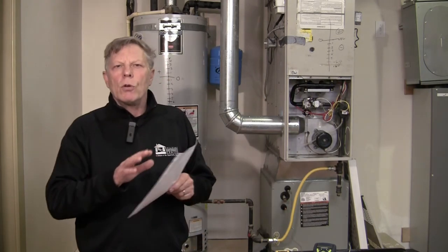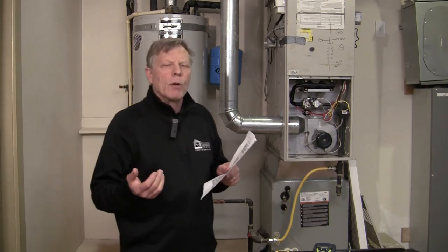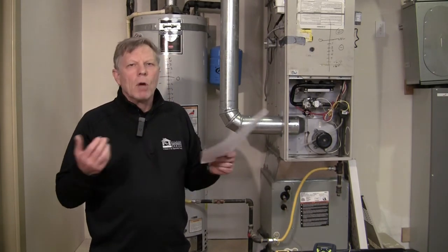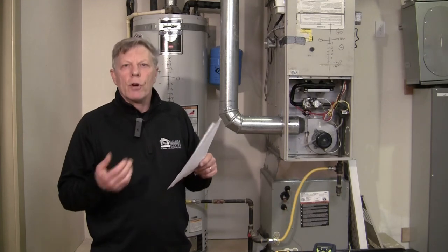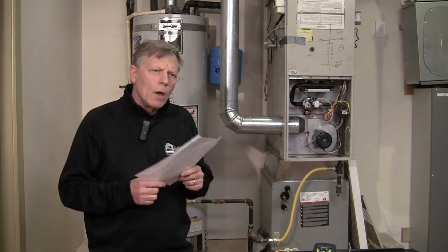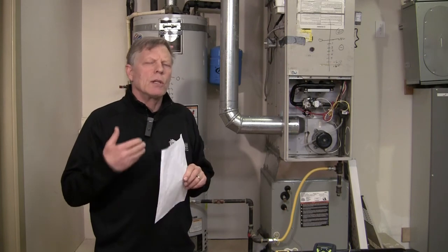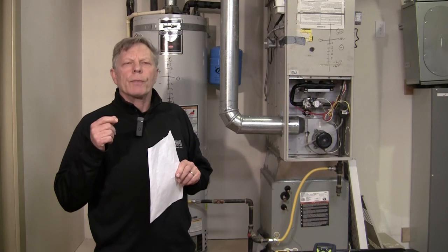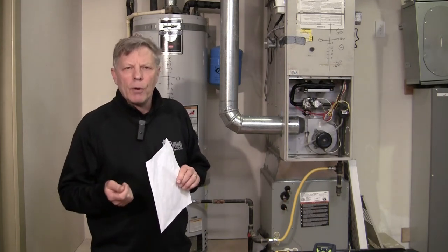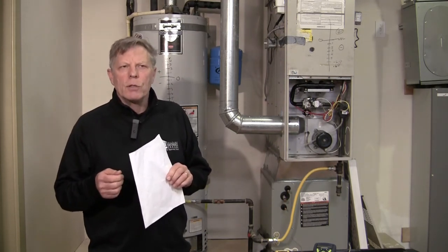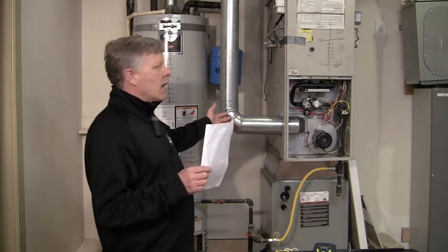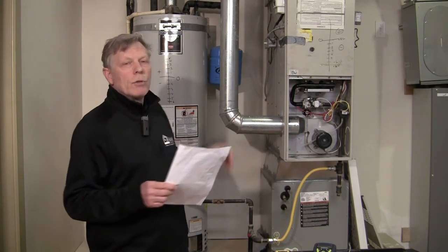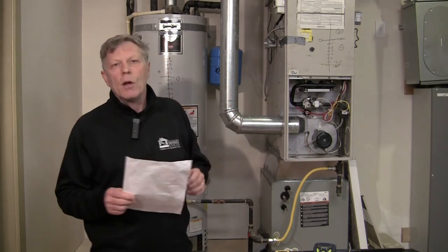The tests that we're going to do: carbon monoxide testing, we're all familiar with that, but that gets done on all of our appliances, ovens, water heaters, furnaces, maybe a boiler. Worst case spillage testing doesn't get done on all appliances. It only gets done on appliances that have a draft hood or barometric damper. Those are Category 1 appliances, and this is a Category 1 appliance here. It's an 80% efficient furnace. It shares a chimney with a water heater with a draft hood, so this one does get tested for spillage.